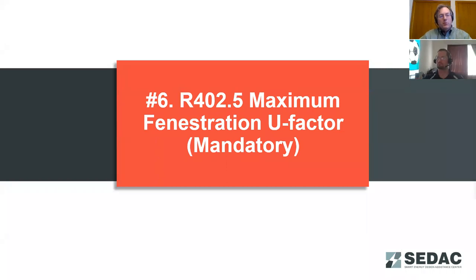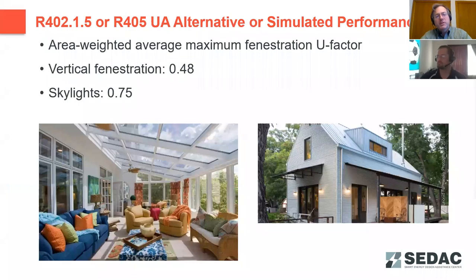So with that, we'll go ahead and keep trucking along here. So overall, we're doing all right. Maximum fenestration U factors. So this is in case you're doing a simulated performance or UA trade-off. The code does call out that there is a maximum U factor that you may have area weighted wise. So for vertical fenestration or windows, maximum of 0.48, and for skylights a maximum of 0.75.